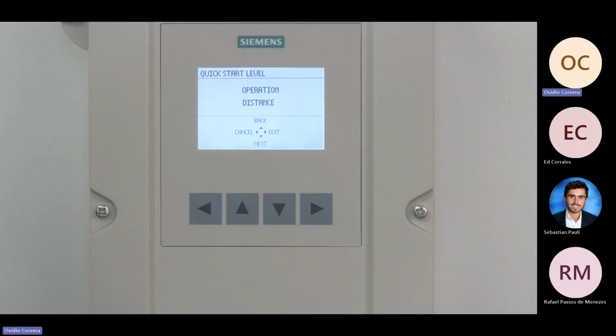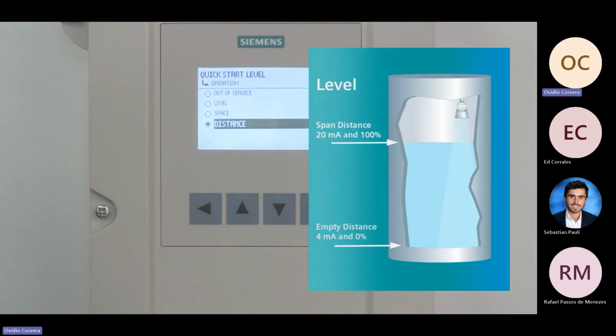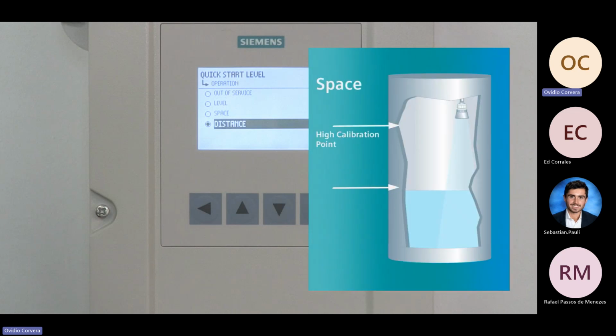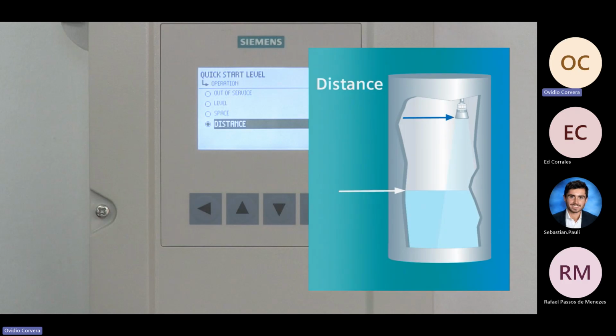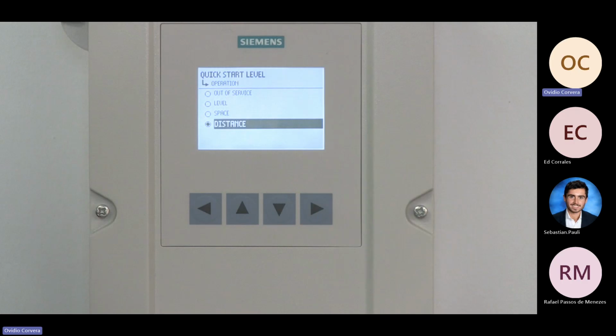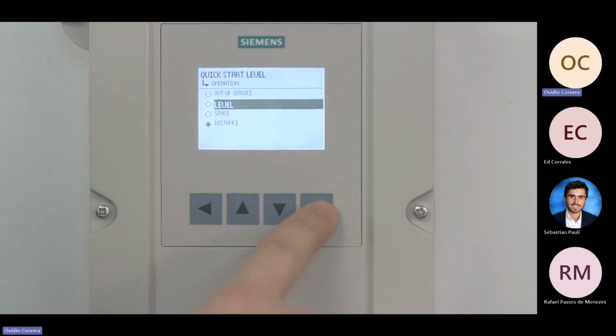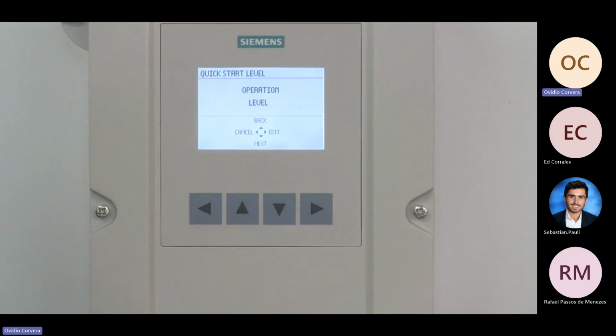Now let's select your mode of operation. The default operation for a single point unit is distance, and the default for a dual point unit is level. Press the right arrow to select Edit to change the mode of operation. Level operation measures the height of material in the vessel from the low calibration point to the high calibration point. Space operation measures the distance between the top of the material surface to the high calibration point. Distance operation measures the distance from the face of the transducer to the top of the material surface. Using the up-down arrows, highlight the level mode of operation and press the right arrow to enter your selection. Press the down arrow to select Next to proceed.